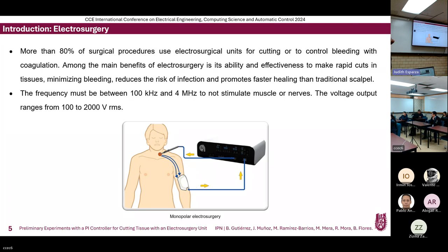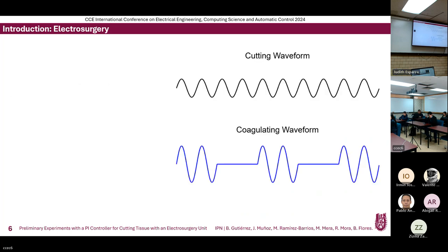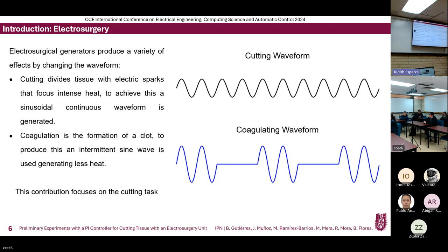To avoid stimulating muscular nerves and causing pain, the frequency range used is between 100 kilohertz and 4 megahertz, and the voltage range is from 100 volts to 2000 volts. The desired effect can be achieved by changing the waveform. The two main operating modes are cutting and coagulation. For cutting, electrosurgery units use a continuous sinusoidal waveform to cause the most heat and cut the tissue. For coagulating, the waveform is an intermittent higher-voltage sinusoidal waveform to produce less heat and form a clot. Our work focuses mainly on the cutting task.